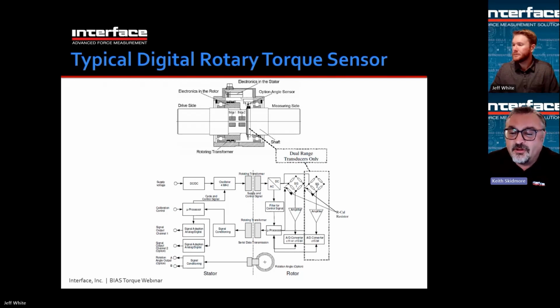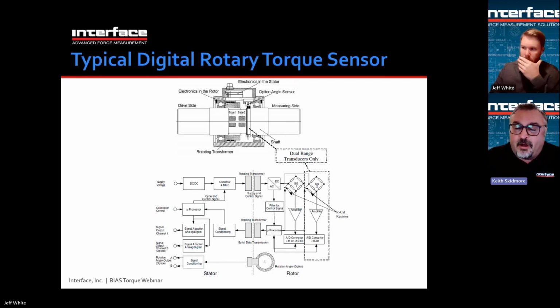Because there's a microprocessor on the shaft, we can also send a command to the shaft to close a shunt. So some rotary torque sensors actually do have the ability to have a shunt on the shaft. It's not possible to connect a shunt resistor across an induction gap, but if we can send a command to the shaft to close a switch, then a shunt can be enabled on the shaft. The advantage of a shunt on the shaft is that it shunts the strain gauge bridge, creates a signal from the bridge, and then that signal is processed and transferred to the stator and amplified into your signal conditioning or external signal conditioning. Basically everything downstream of the bridge can be checked, double checked, or used for scaling.